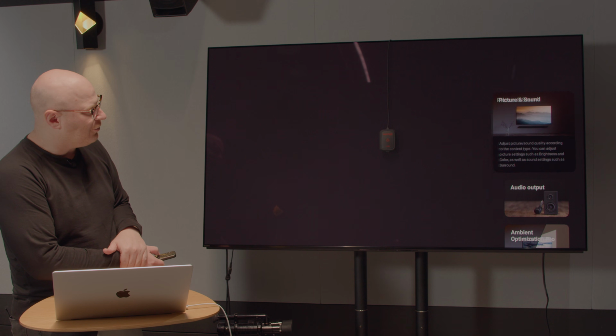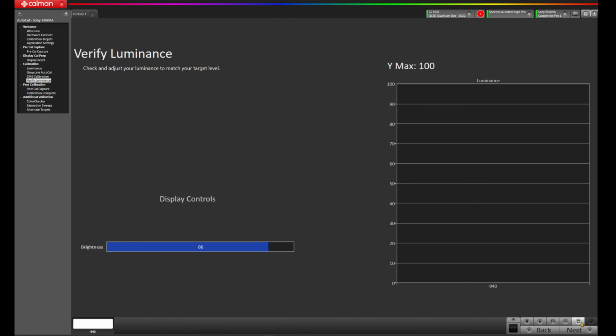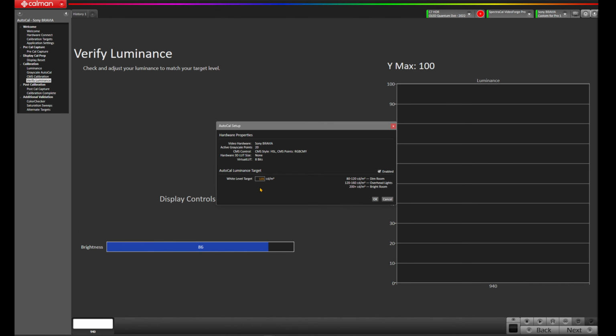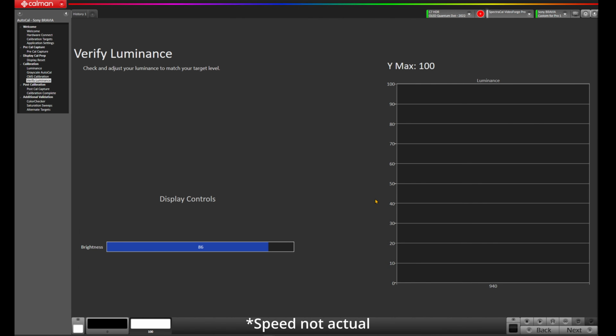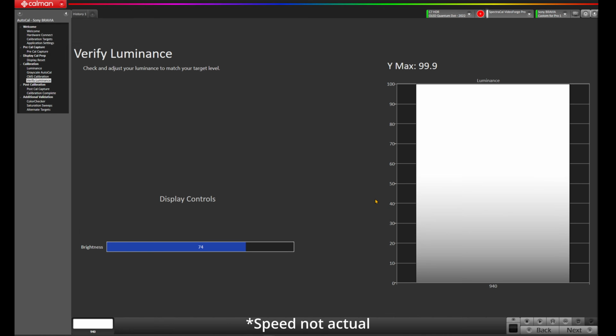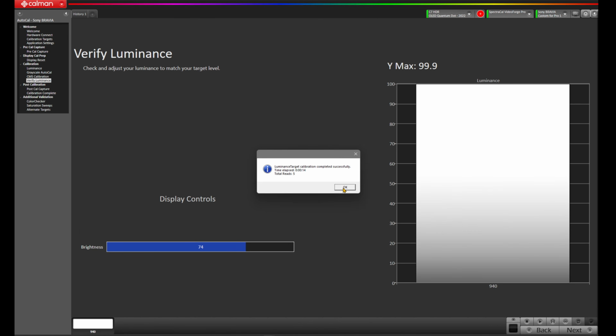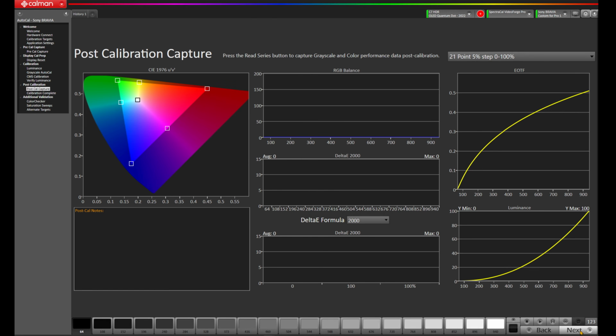That's going to reduce a little bit of luminance here. Now we'll back out of the menu. And my calibration target, because we're in this reference review room, is going to be 100. So we'll come down to the AutoCal button in the bottom right, set the white level target to 100, and press OK. Okay, our calibration completed successfully. The time elapsed is 14 seconds, total reads of 5. Let's press OK, press Next, and now we're at our post-calibration capture.